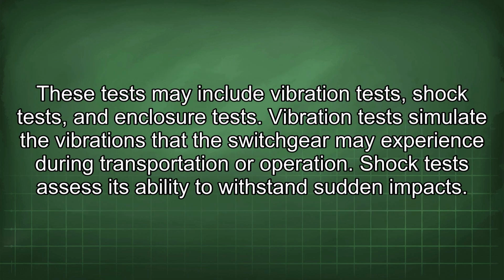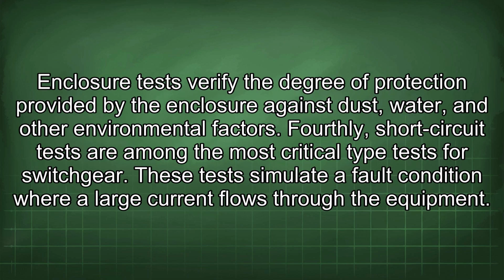Thirdly, mechanical tests evaluate the structural integrity and durability of the switchgear. These tests may include vibration tests, shock tests, and enclosure tests. Vibration tests simulate the vibrations that the switchgear may experience during transportation or operation. Shock tests assess its ability to withstand sudden impacts. Enclosure tests verify the degree of protection provided by the enclosure against dust, water, and other environmental factors.